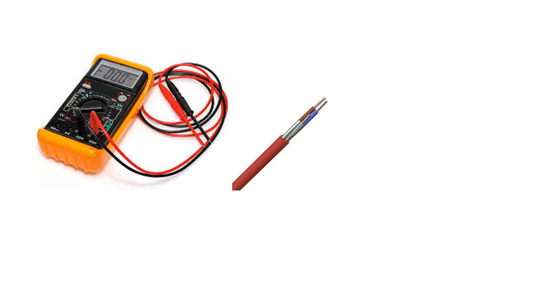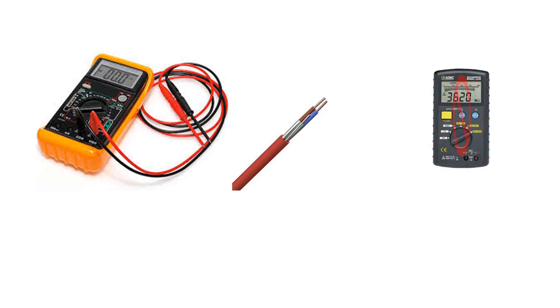Check all wiring for continuity. Short circuits and open circuits must be rectified before connecting the wiring to the control panel. When devices are connected, all cable testing must be carried out with a multimeter, not a megohmmeter. Induced voltages greater than 1 volt indicate possible cable problems or bad earth connections and must be rectified before devices are connected. Check detection zone cables.